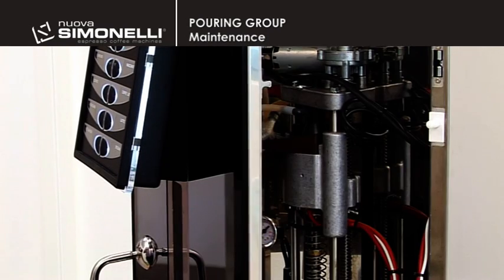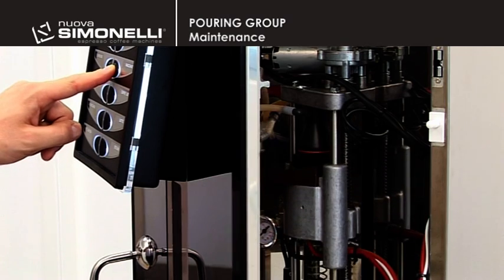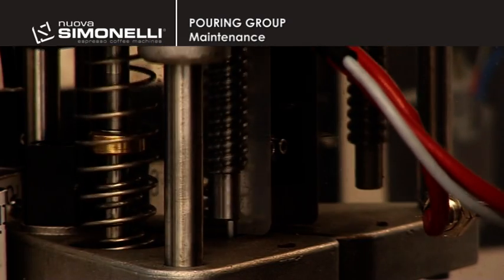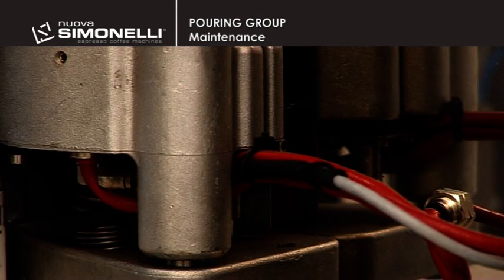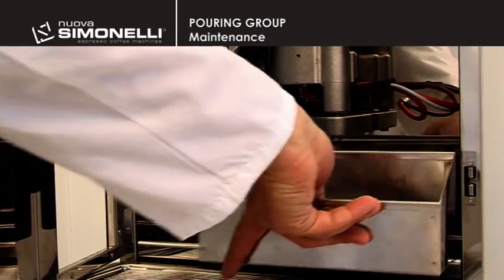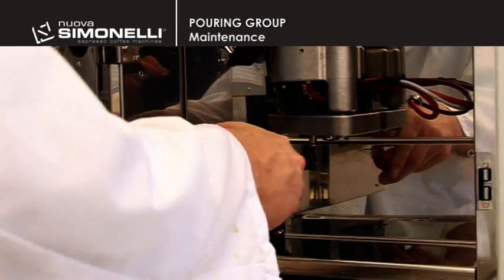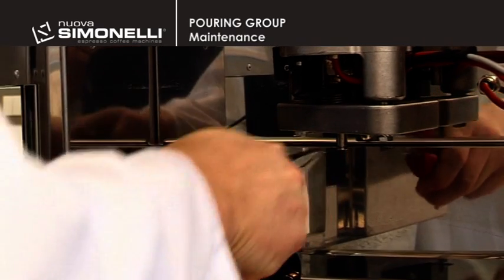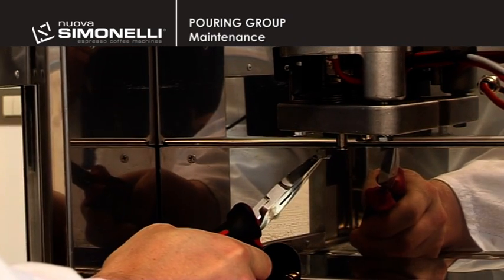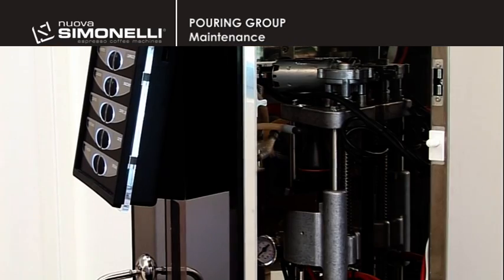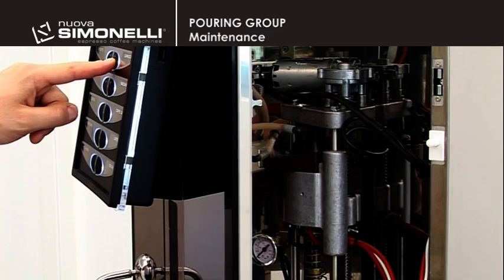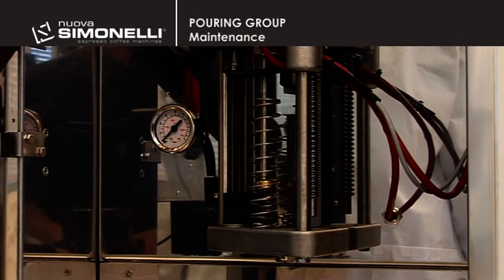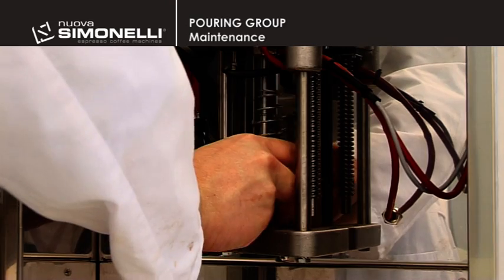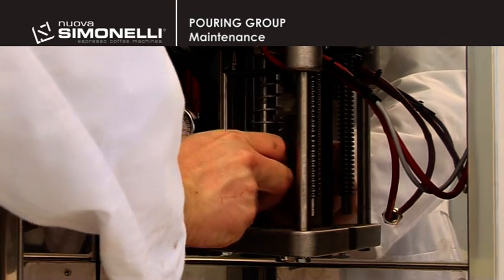To replace the seal on the bottom piston with the machine door open, press 7 and move the chamber to the bottom position. Remove the drawer and take off the bottom O-ring with a pair of pliers. Press the number 6 key to move the chamber to the top position. Slide out the springs and remove the central O-ring on the bottom piston shaft.